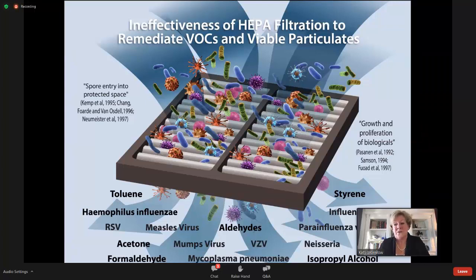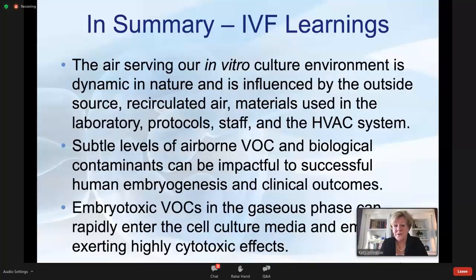They need two things, food and water. Food is often the other organics, or depending upon the filter, it could be the matrix itself. Water is simply the humidity in the air. So you're capturing these organics above the space you're trying to protect, and they're continuing to grow. With high velocity going through those filters, they have the potential of entering your space. In addition, a lot of your smaller bacteria and smaller viruses are not going to be 100% captured by these final filters, and all of your VOCs are going to go through the media.